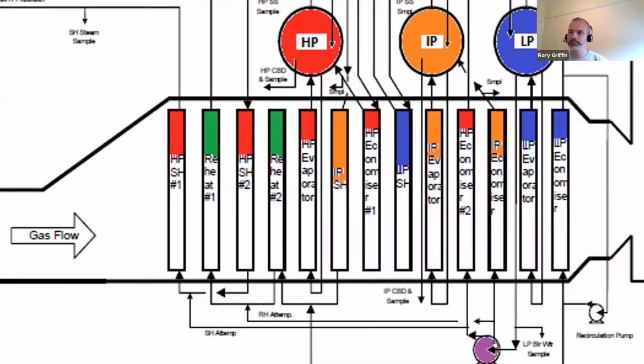This is a multi-stage pump. So at 27 bar pressure, about 70 tons heads off up the intermediate pressure economizer. And of the 70 tons, about 40 to 45 gets diverted to the gas performance skid. So this is the water that's used to heat the gas going into the gas turbine. That's about 40 tons per hour.